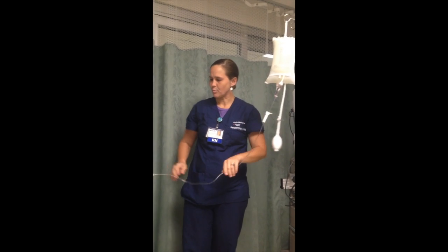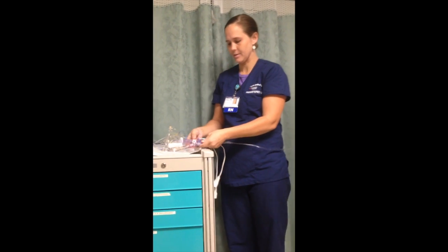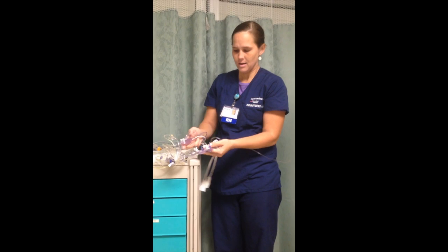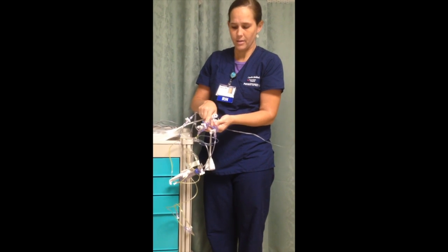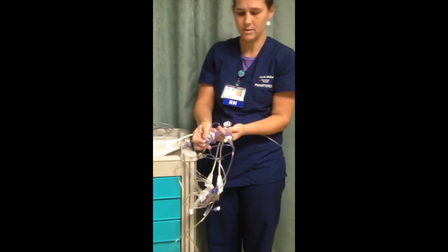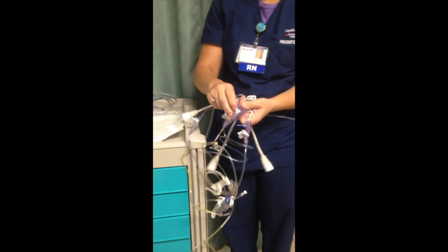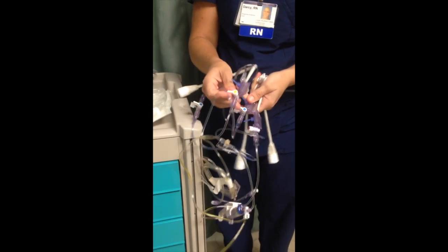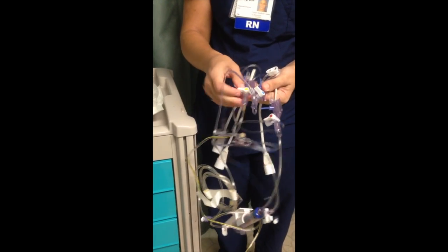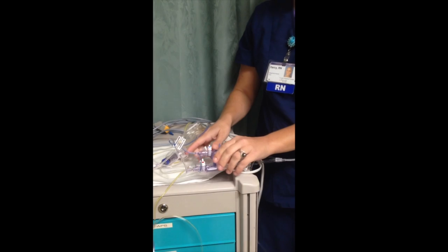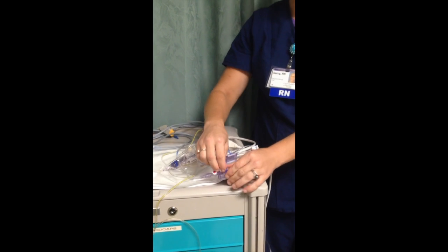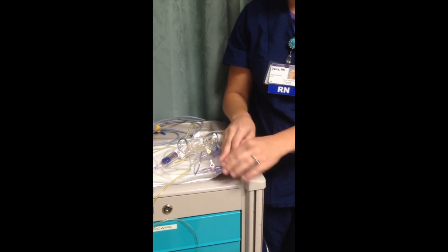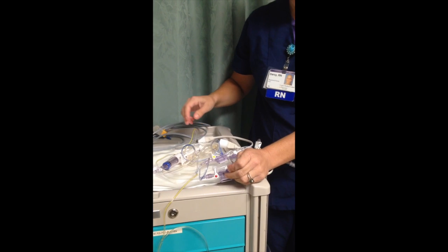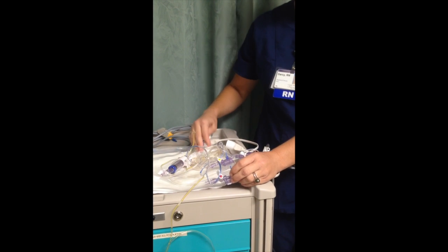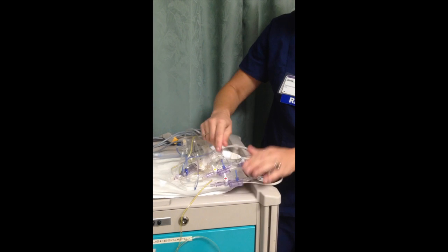Once you've done that, you need to prime the tubing, and on this one we have a transducer for each line. They're color coded for us already, so we have the red one for the A line, the blue one for the CVP, and the yellow for the PA line. To prime the tubing, you simply pull the pigtail on each one until the saline comes out the end, like so.